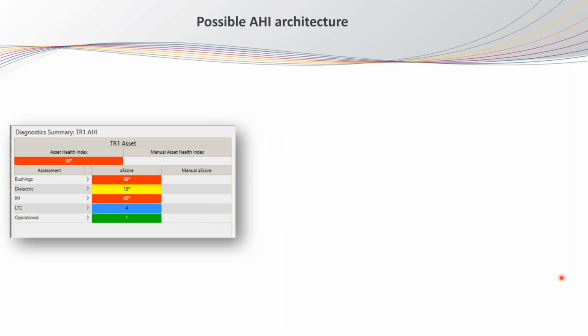While we are dividing the asset into a number of subsystems, identifying failure modes, and considering the group of analytics, the reason is that you, as a user, can easily identify the reason behind a high health index, or find out why this transformer's condition is not good. As an example, if we have a transformer with a high asset health index, we can look at the different subsystems. We can say the bushing score is quite high, so it means the condition of the bushing is not good, and the insulating material, which refers to the DGA and oil quality, also doesn't show a good condition.